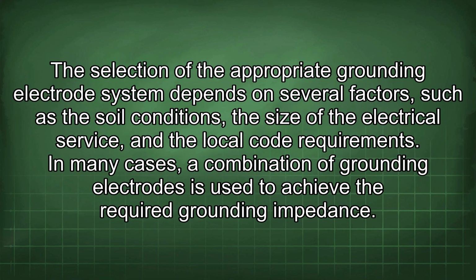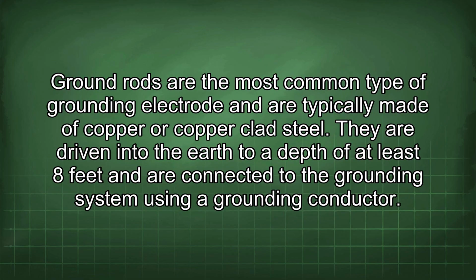The selection of the appropriate grounding electrode system depends on several factors such as the soil conditions, the size of the electrical service, and the local code requirements. In many cases, a combination of grounding electrodes is used to achieve the required grounding impedance. Ground rods are the most common type of grounding electrode and are typically made of copper or copper-clad steel. They are driven into the earth to a depth of at least 8 feet and are connected to the grounding system using a grounding conductor.